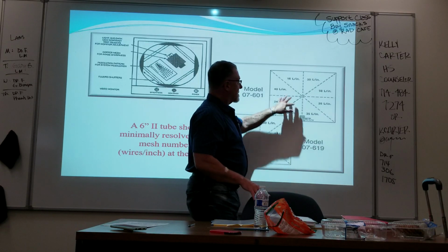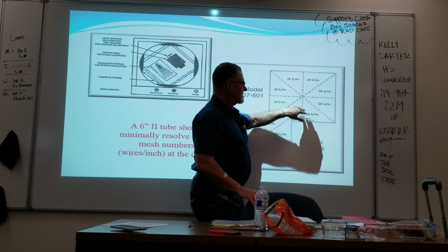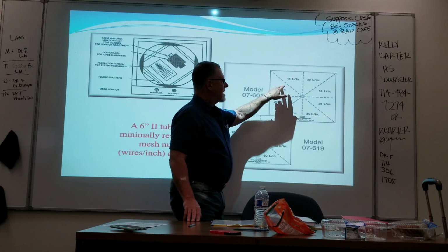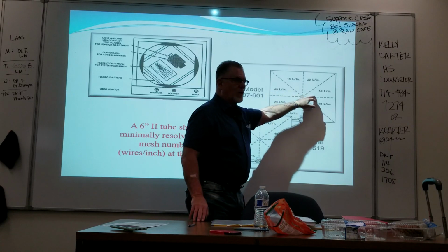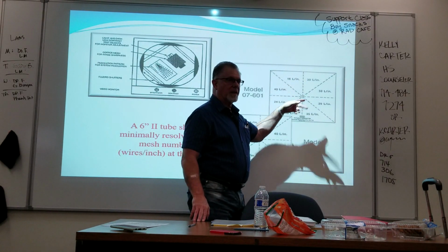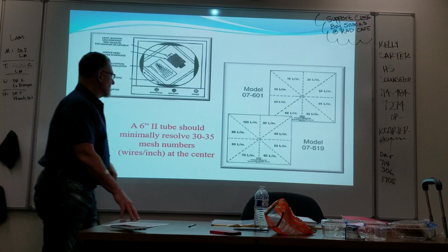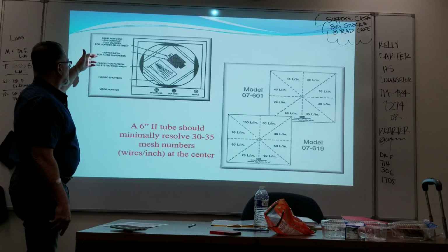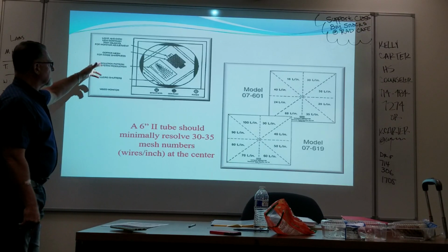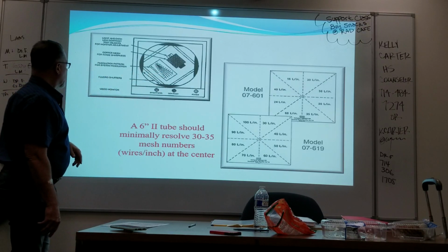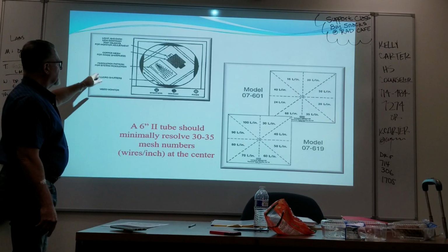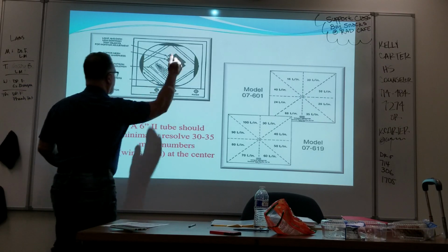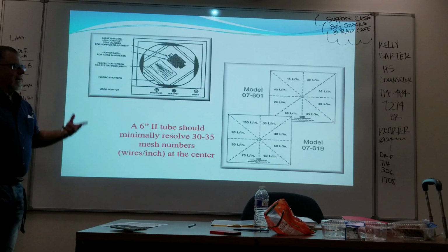For the system in the back, you're going to be looking at both center and at the edges. They will be different. You also want to check to see, is it clear in the horizontal direction but blurry in the vertical, or vice versa. That's important to know. You've got more complicated patterns. You can put things in that have copper mesh to look at sharpness. You've got resolution patterns that actually measure line pair resolution. You've got indications for where your fluoro shutter should be. You can have low contrast and high contrast input.